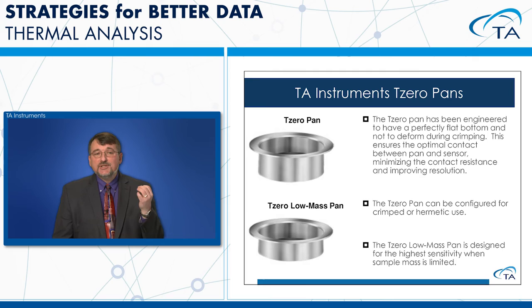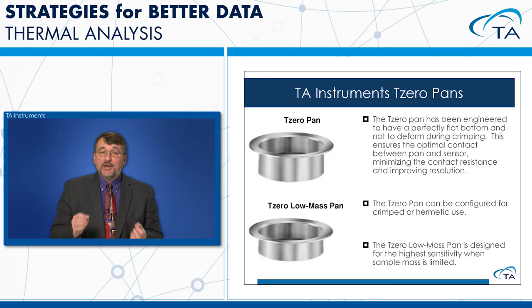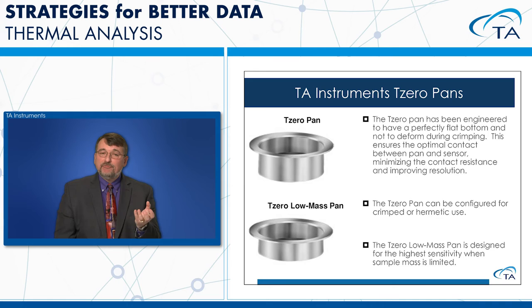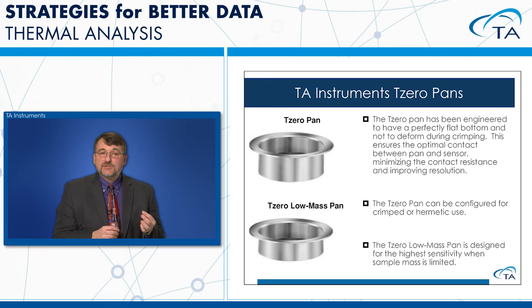The Tzero pans from TA Instruments have been engineered with an extremely flat bottom that sits on the flat sensor, giving the best thermal contact and performance. The pans start flat and remain flat even after loading a sample and lid. Tzero pans can be configured with a standard crimped lid or a hermetic sealed lid to keep volatiles in. There is also a low-mass Tzero pan for very low-mass and thin samples.